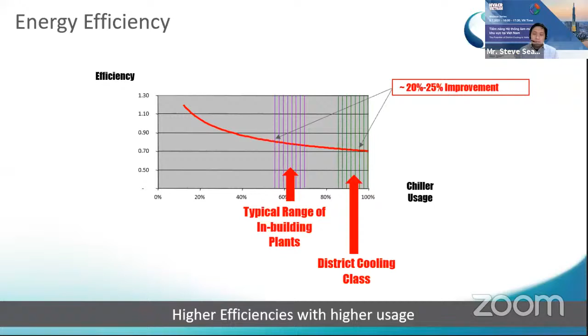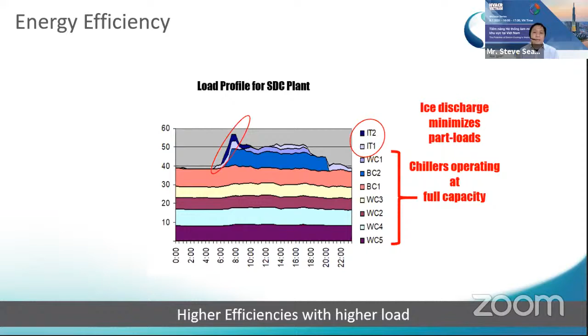We have also been able to constantly load and operate our equipment at full capacity and at its most efficient point through the use of thermal storage, both ice thermal storage and chilled water thermal storage. This reduces the need to operate an additional chiller under part-load inefficient conditions. The issue many in-building chillers face today does not apply to a district cooling plant.